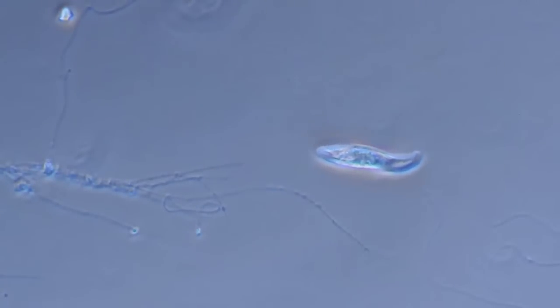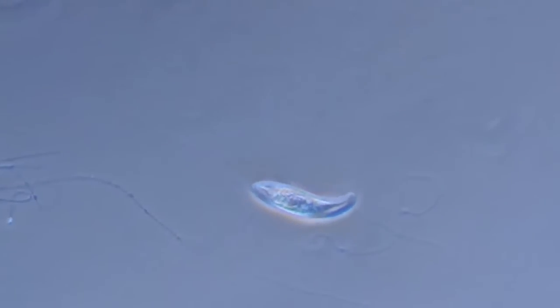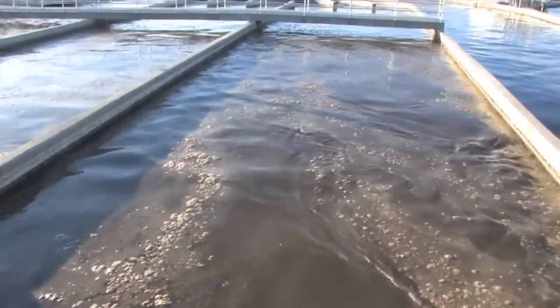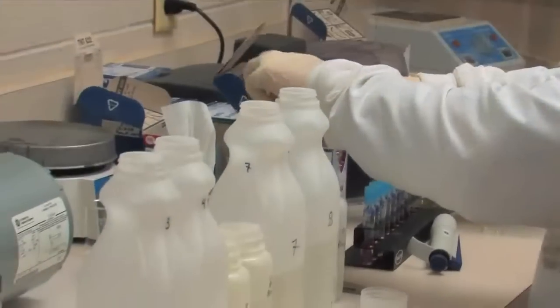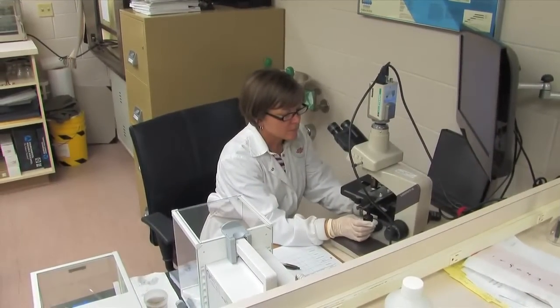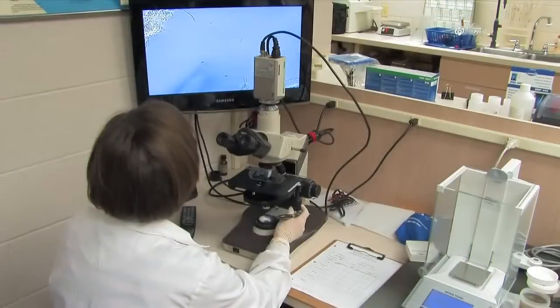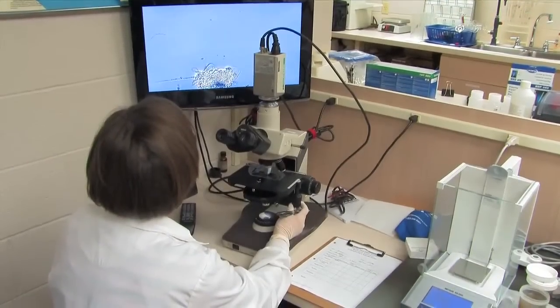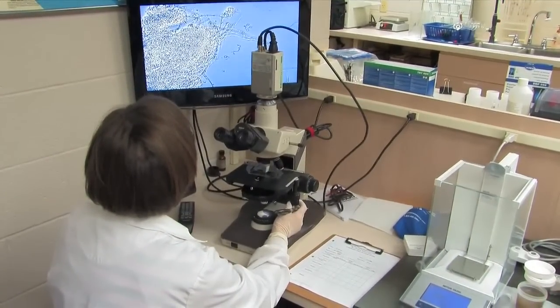Once you identify and track indicator organisms, you can change the conditions you have control over, such as the mixed liquor concentration, aeration, RAS flow, pH adjustments, and nutrient deficiencies. It may take some effort, but it could help you do what you do better. And the better you operate, the cleaner the water is. And that makes it all worth it.